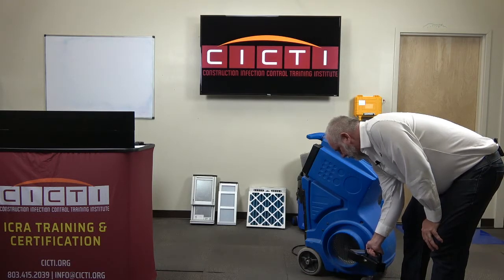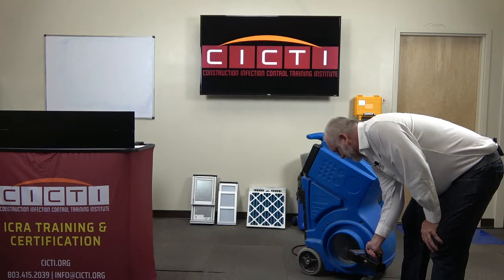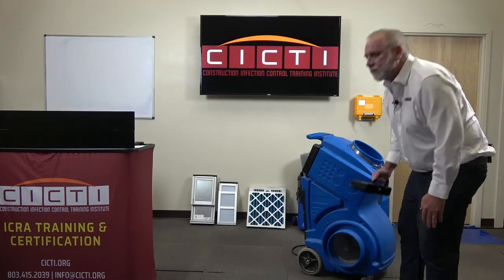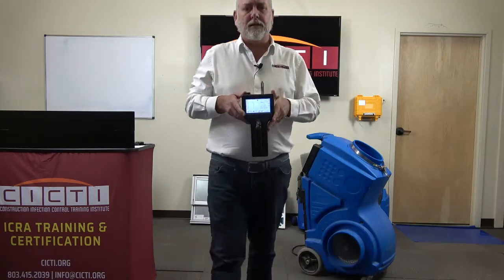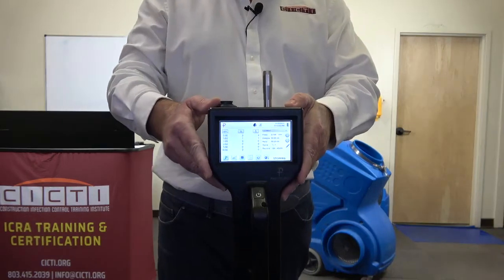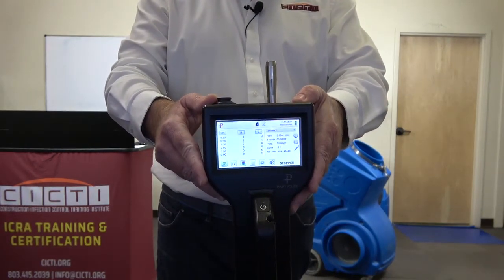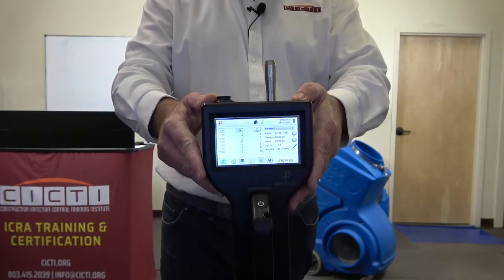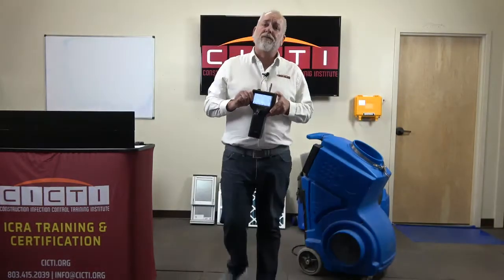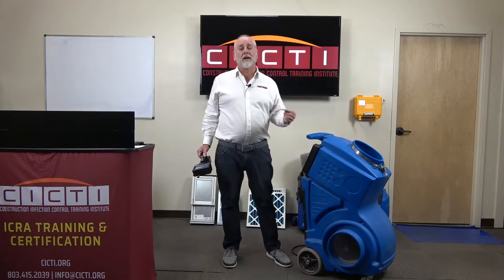airflow. I've got 12 seconds left on my sample, and 7 seconds left on my sample, and 3, 2, 1. Okay, if memory serves, it was 15,301 going in. So anything less than 153 is good. So now let me get close to this camera again, and hopefully you can see the numerical value of 4 in that top middle reading on the screen of the particle counter. 4. So out of 15,301 going in, I only have 4 coming out. That's well above 99% efficient. And in this case, this device passes.